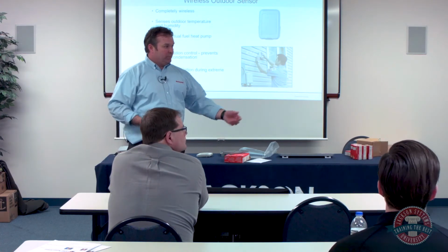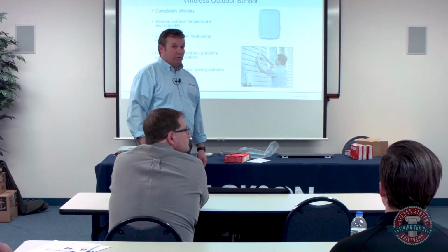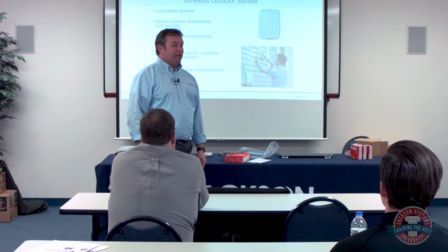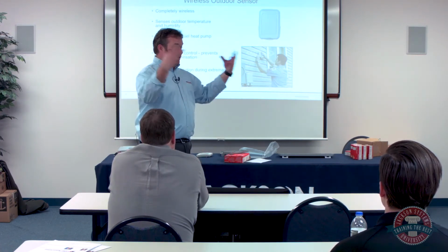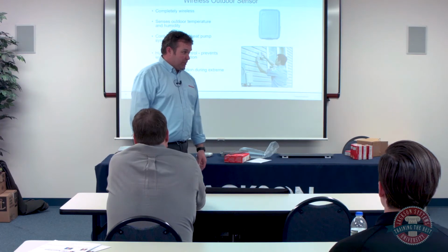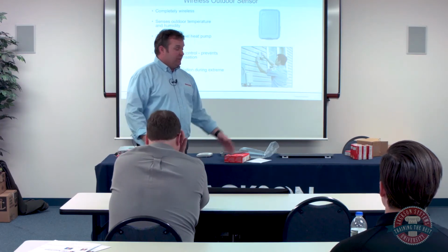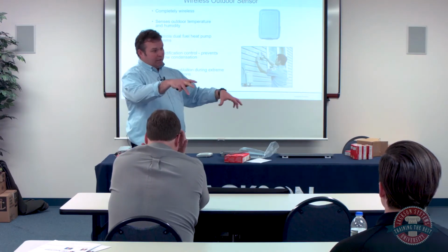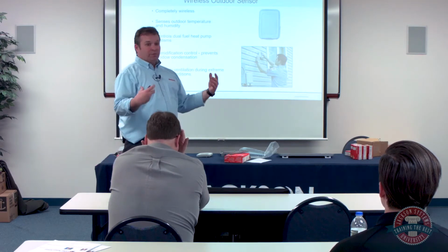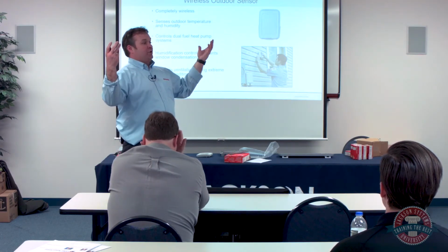You can set that to economize for you. It's a ventilation limit, so you're not sucking in 100-degree air from outside and ruining your Delta T. When it gets back down to 80 degrees or something your system can handle, then you can allow it.